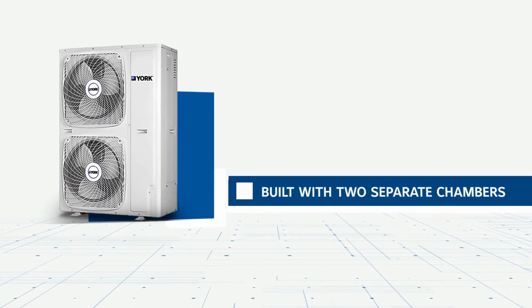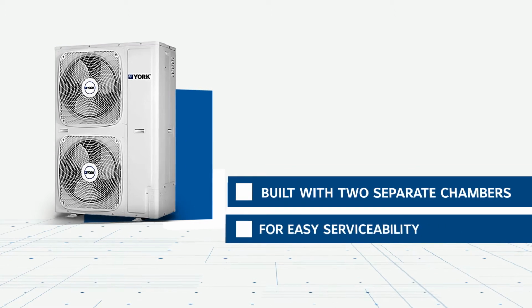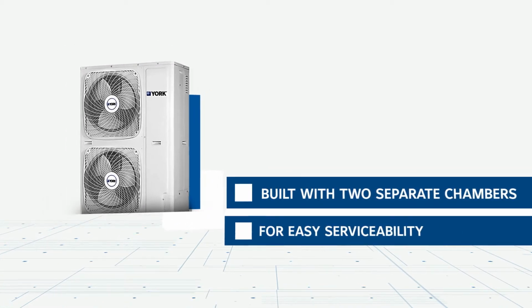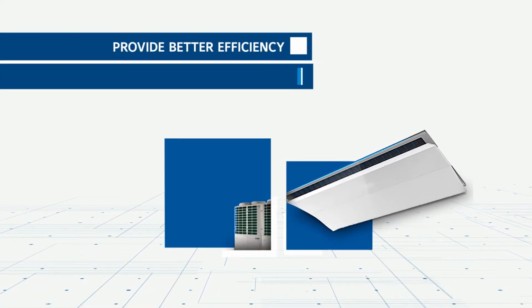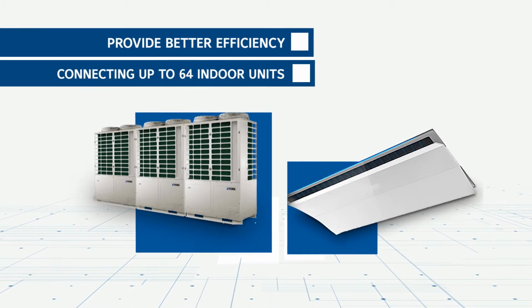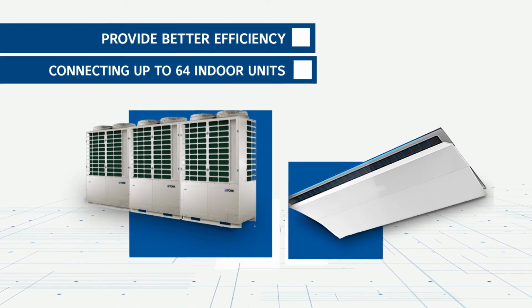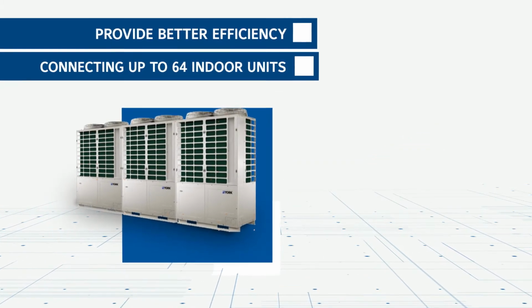Our VRF systems are built with two separate chambers, one for compressors and PCB board and another for condenser, for easy serviceability. The four-way heat exchanger and high-efficiency DC inverter scroll compressors provide better efficiency and are capable of connecting up to 64 indoor units per refrigeration circuit consisting of three outdoor units.